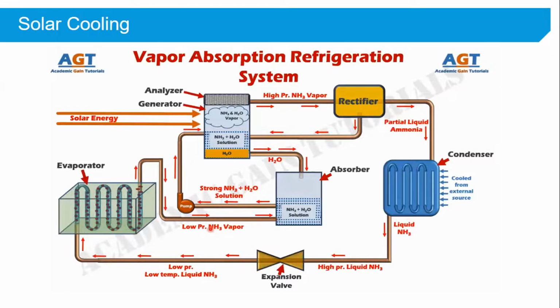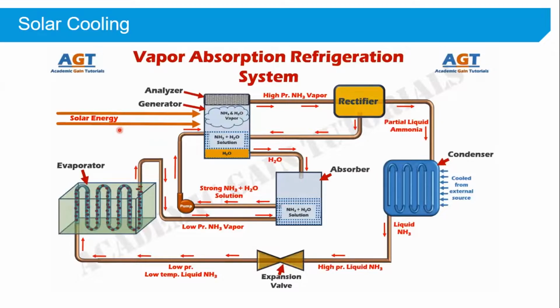Then again, this low pressure ammonia vapor will form a solution with the water present in the absorber. The pump will again send this solution to the generator, where the heat generated by solar energy will again form ammonia vapor and water vapor. Then again water vapor is sent back to the absorber. Ammonia vapor passes through the analyzer to the rectifier, and the whole cycle keeps happening over and over again. And thus refrigeration occurs continuously in the evaporator, and the surrounding space keeps cooling continuously. So, this is how a solar vapor absorption refrigeration system works, where solar energy is used to obtain the cooling effect.